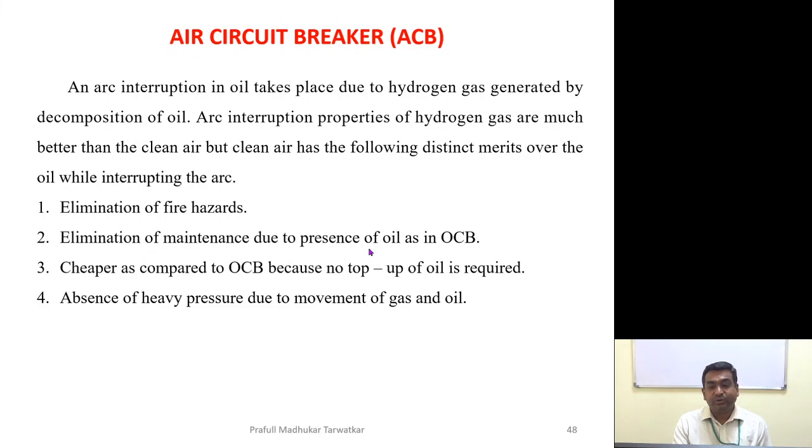Elimination of maintenance due to presence of oil, as in the case of oil circuit breakers. Definitely, oil-immersed transformers or oil-immersed circuit breakers need periodic maintenance, because the chemical properties as well as the electrical properties of the oil deteriorate as time goes on. They need to be replaced, and that replacement of the oil is costly.